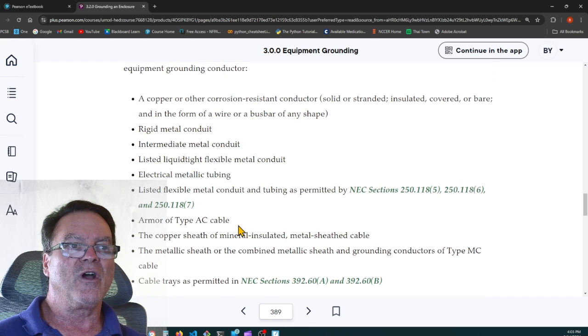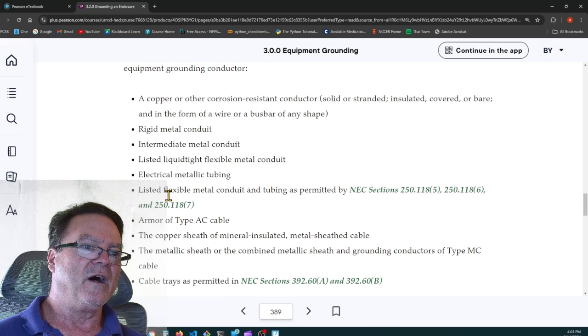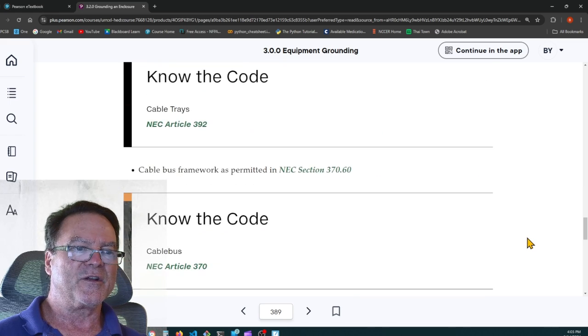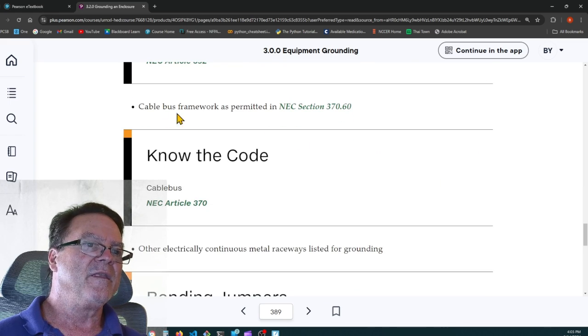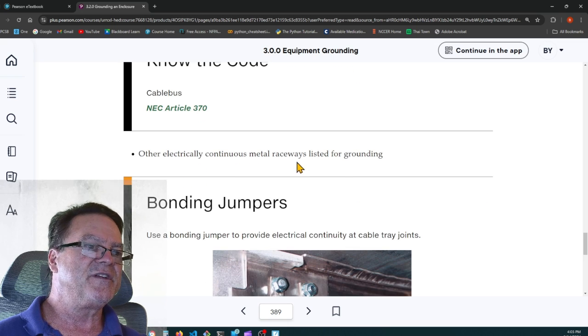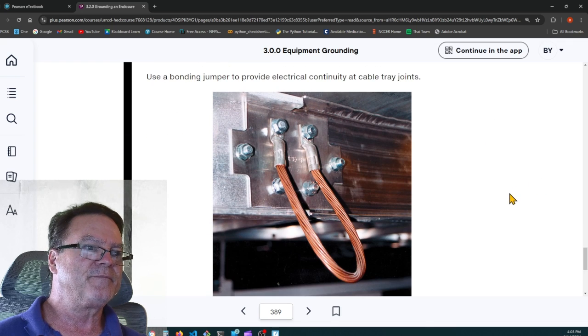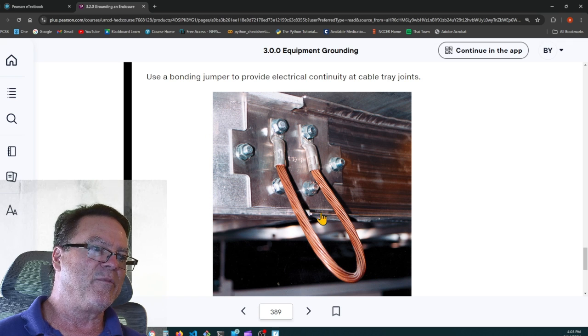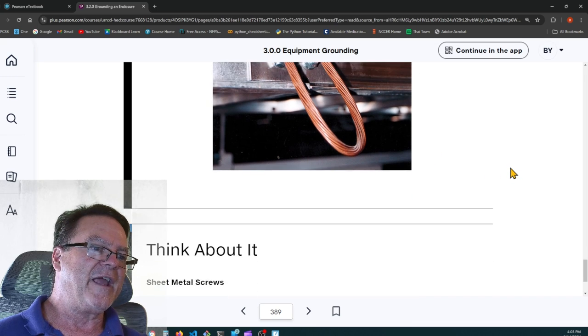Again, check with local codes. The municipality may not allow you to use rigid, intermediate, or EMT as an equipment grounding conductor. Cable bus framework is permitted in NEC section 370.60. Other electrically continuous metal raceways listed for grounding. So here's a jumper across the seam of cable tray. They have a splice plate, but you can't rely on the splice plate for grounding. So you put a jumper across the seam, the connection of the cable tray.